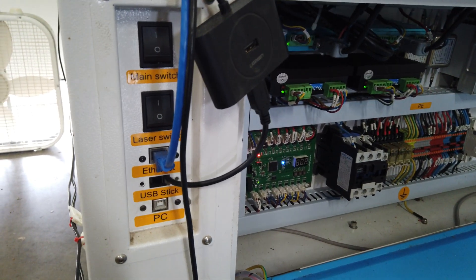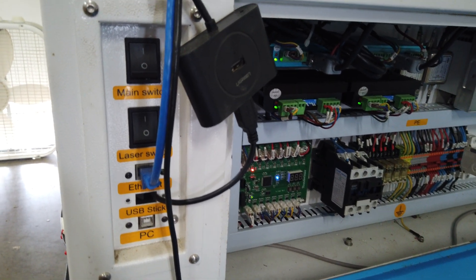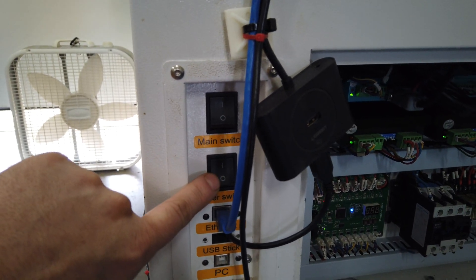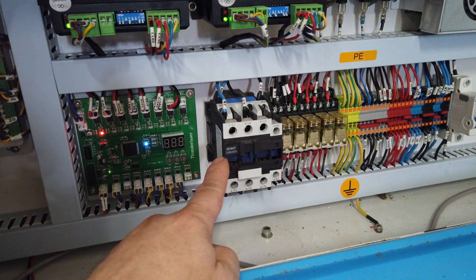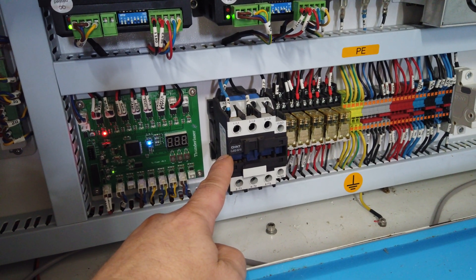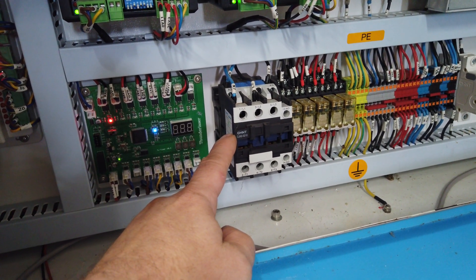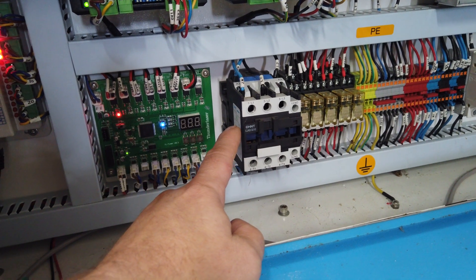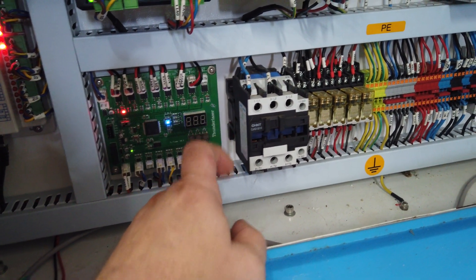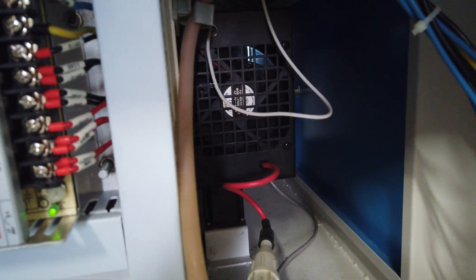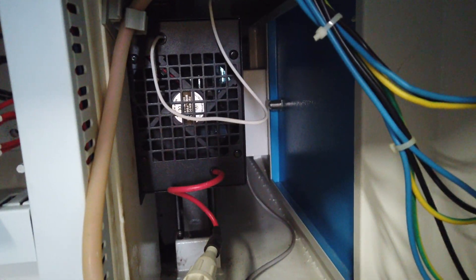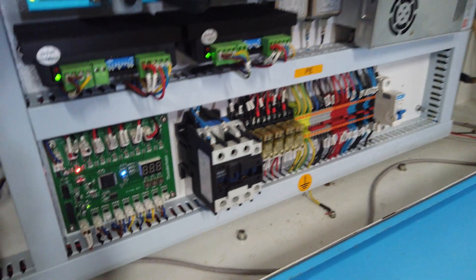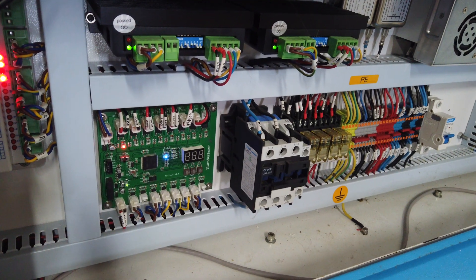Okay, so here's how the contactor works. The laser power switch energizes the contactor, and the contactor is just a big huge relay. It provides power to only two things: the laser power supply right there in the back with the big red wire coming out of it, and the power to the chiller on machines that have the chiller power on the back of the machine instead of plugging in the wall on its own.